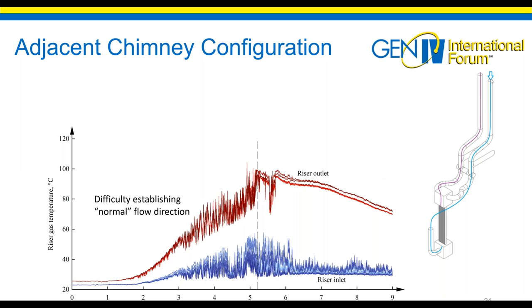In this test, we found quite a bit of effect here, and this was also weather dependent. During startup of your plant, if this is your configuration, you have to keep this in mind, because we showed difficulty establishing normal flow conditions. The blue is the inlet, drawn from the high bay, and red is the exit temperature from the system. You can see there is interplay between these two as we start up, with some oscillatory behavior where the hot exhaust gas is drawn into the inlet, causing rapid fluctuations in the heat-up transient.